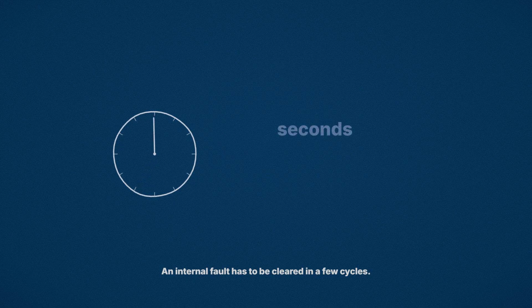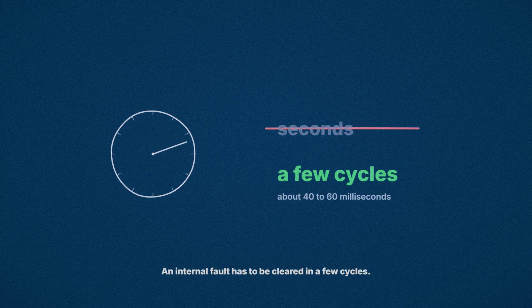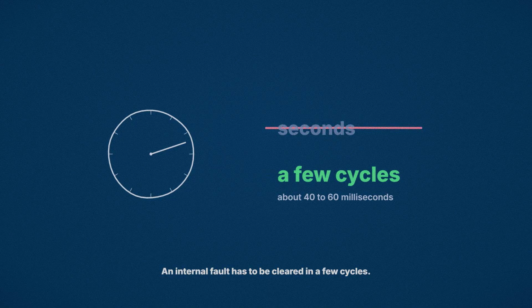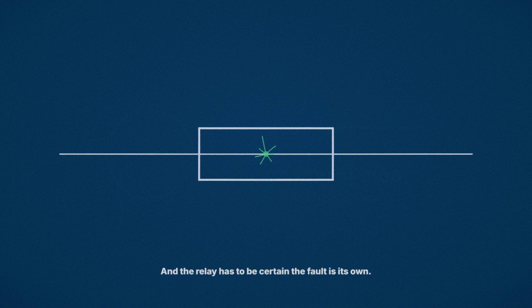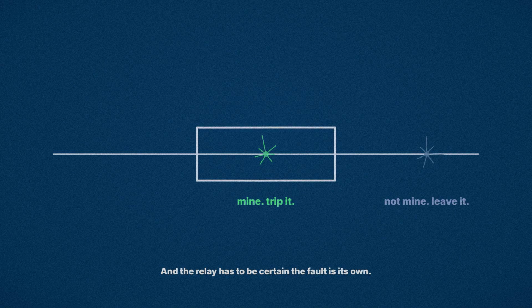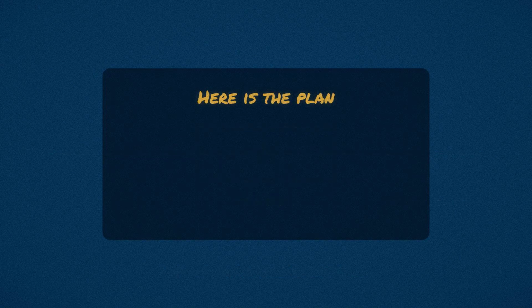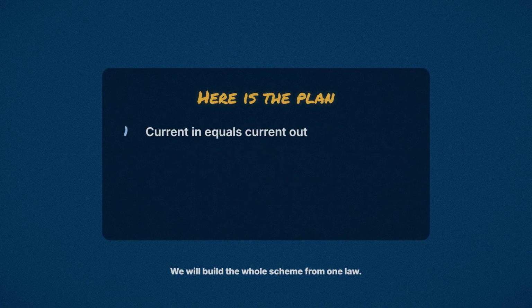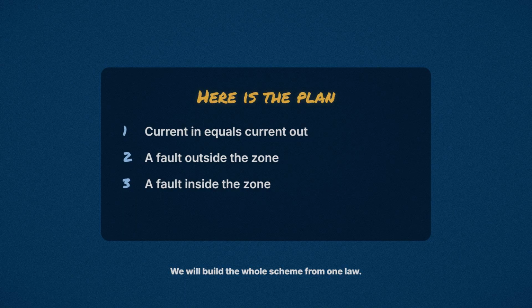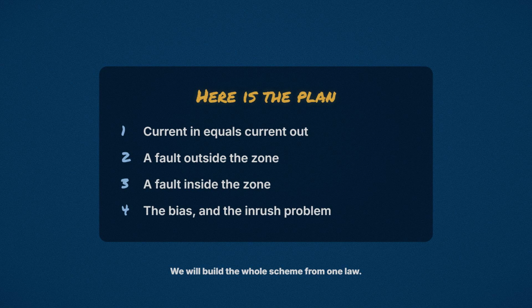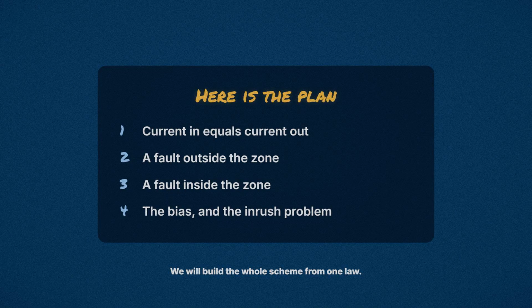Not seconds, cycles. And the relay has to be certain that fault is inside the transformer, because tripping for a fault somewhere else takes healthy equipment off the grid for nothing. In the next few minutes, we will build the whole scheme from one law. Current in equals current out. Then we will follow that current through a fault outside the protected zone and a fault inside it. We will see why a real relay needs a restraint, and what happens the moment a transformer is switched on.